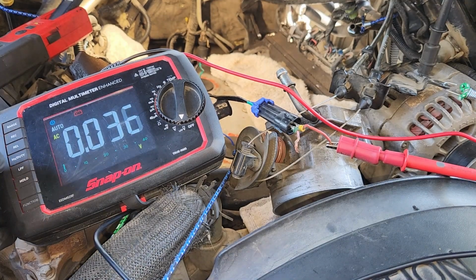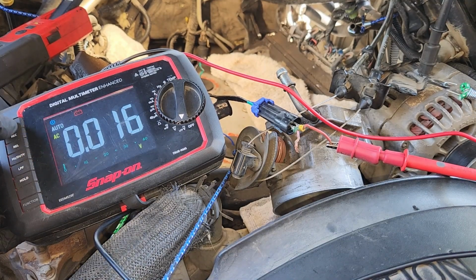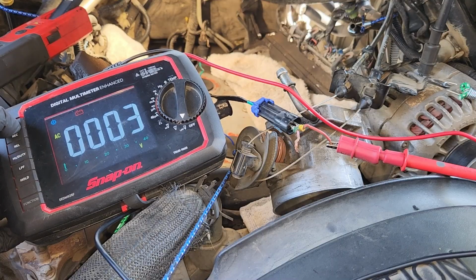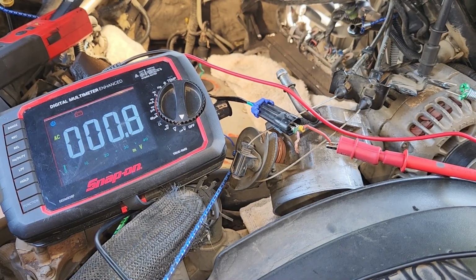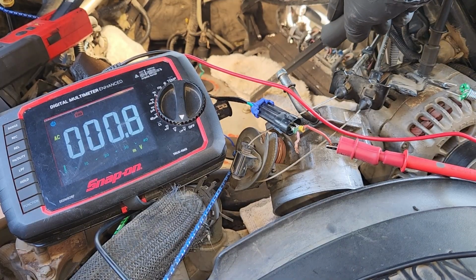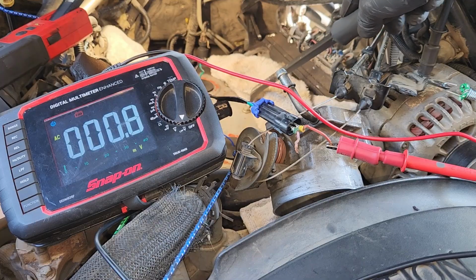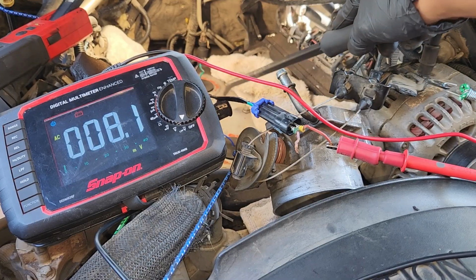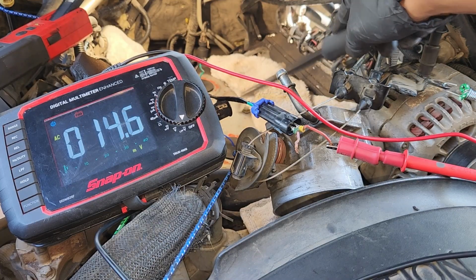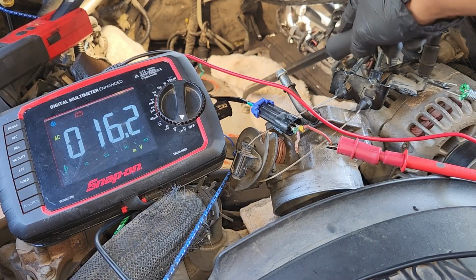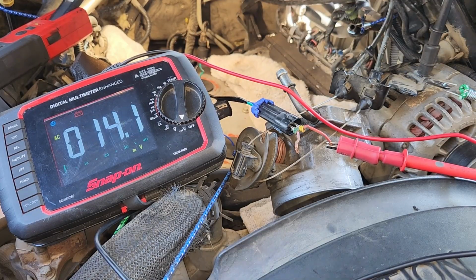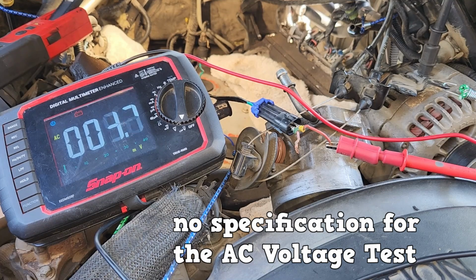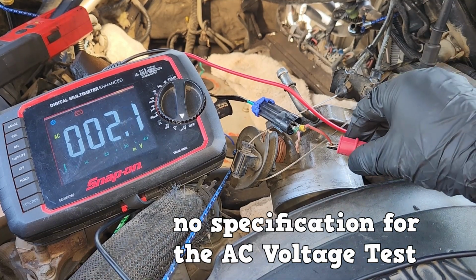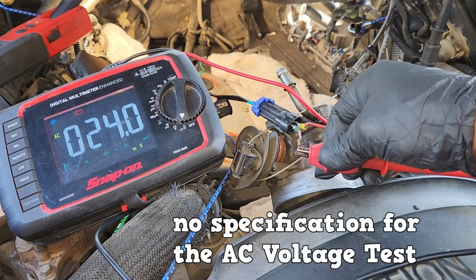Now we're going to go to AC voltage, set at the millivolt scale. We're going to tap this middle bolt in between the 2 sensors and see what we get, lightly tapping it. Average about 15-ish, I saw 20 millivolts. There is no specification for this test, but we know that it's generating AC voltage.